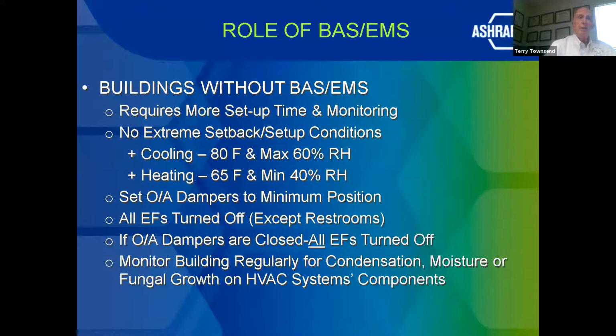Without building automation systems, it requires much more time to set up and monitor. This is physical monitoring, and so you cannot have extreme setback or setup conditions. The best that you can do is 80 degrees F and 60% relative humidity for cooling, 65 degrees F and 40% relative humidity for heating. And you have to set the outside air dampers usually to a fixed position or minimum position, but all exhaust fans are physically turned off, except in the restrooms and during unoccupied modes. So the key thing, though, is without a BAS or EMS, you have to monitor the building regularly for condensation, moisture, or fungal growth on HVAC system components as well as the facility itself.